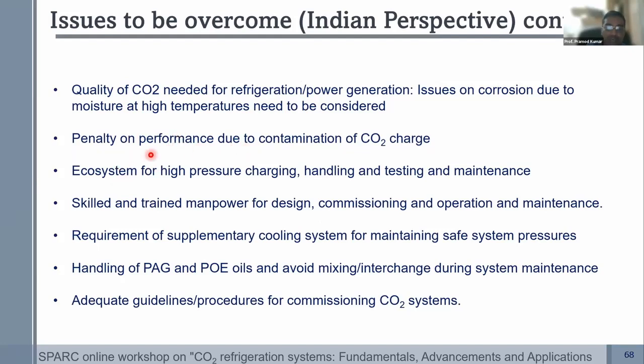So it does have a penalty on performance due to contamination of carbon dioxide. But how much is it? We don't have an answer. The big flip side is that contamination in carbon dioxide can completely offset the inbuilt parameters in your controllers, because they all assume that the carbon dioxide you're filling in is pure. So there are issues of that sort.